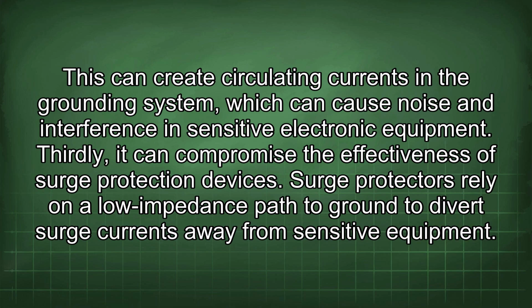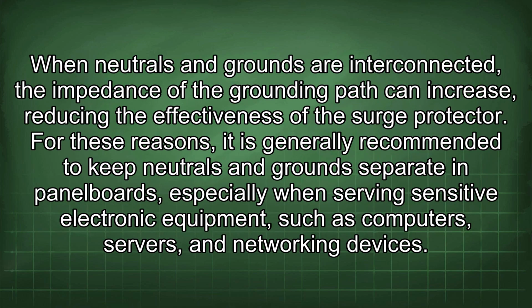Thirdly, it can compromise the effectiveness of surge protection devices. Surge protectors rely on a low impedance path to ground to divert surge currents away from sensitive equipment. When neutrals and grounds are interconnected, the impedance of the grounding path can increase, reducing the effectiveness of the surge protector. For these reasons, it is generally recommended to keep neutrals and grounds separate in panel boards, especially when serving sensitive electronic equipment such as computers, servers, and networking devices.